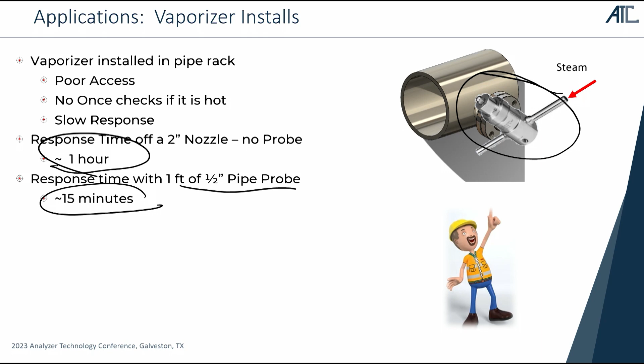So when we have vaporizers up there, and they're coming right off of a pipe nozzle like this, they can have a lot of time delay before we get into the vaporizer, and really slow response times. Like I said, I went through the calculations. On a 2-inch pipe nozzle without a probe, you probably have an hour of time delay getting into the vaporizer. If you add a probe about 1 foot long of 1/2-inch schedule 80 pipe, you might be down to 15 minutes. Big time delays up there. These vaporizers only run at a few milliliters a minute.